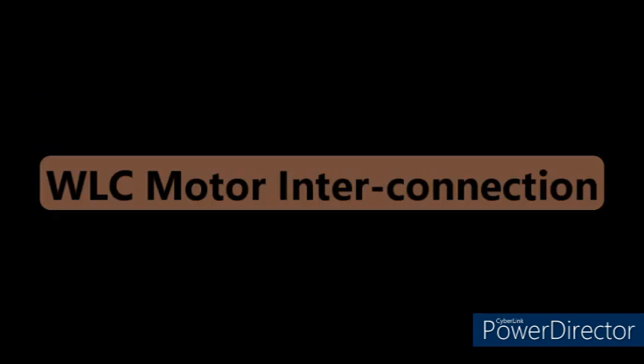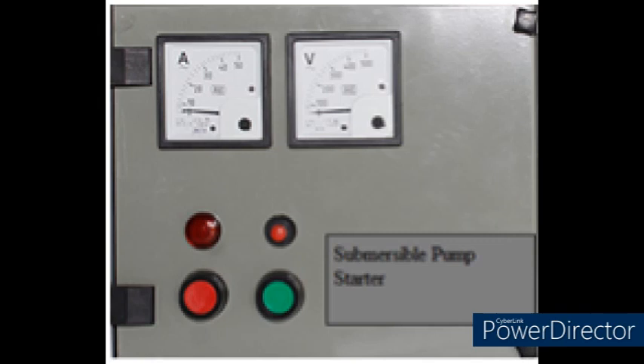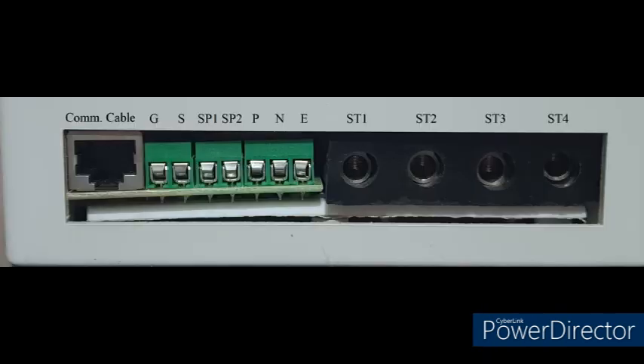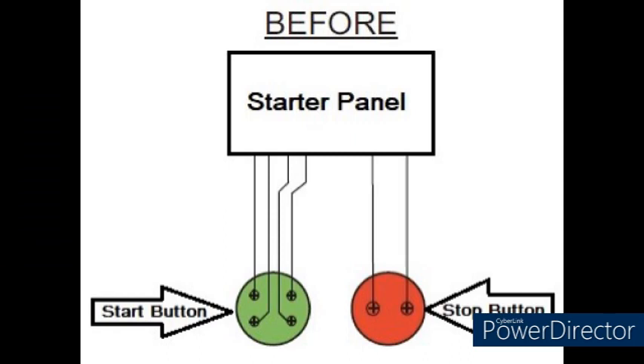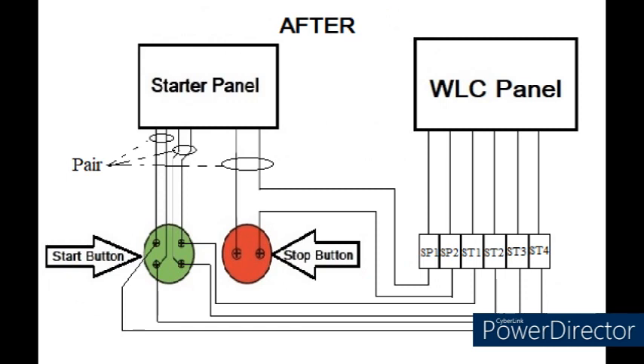WLC and pump feeder interconnection. If the feeder is a starter panel, that is, it has separate start and stop buttons, SP1 and SP2 pins of WLC are connected to the stop button of the feeder panel in series. If the start button has 4 terminals or 2 pairs like shown, the ST1 and ST2 pair is connected to 1 pair of the start button in parallel and the ST3 and ST4 pair is connected to the other pair of the start button as shown. However, if the start button has just 1 pair, connect it to the ST3 and ST4 terminal pair of WLC.